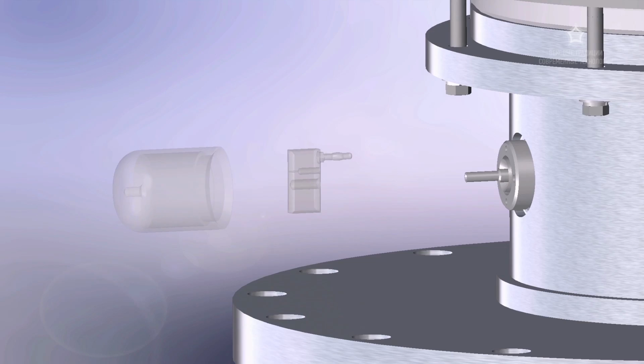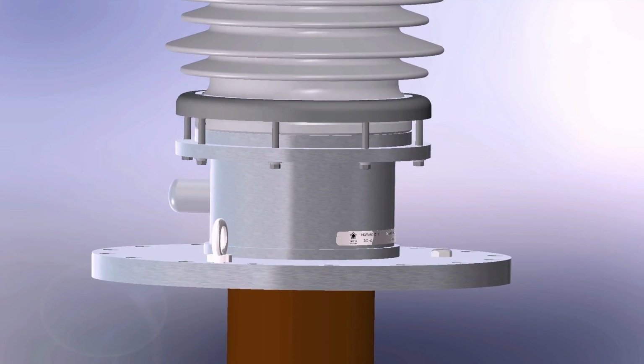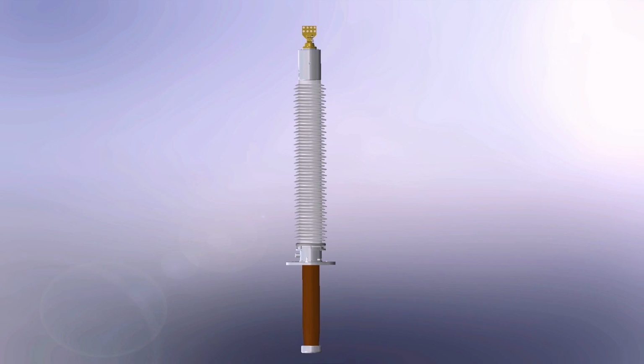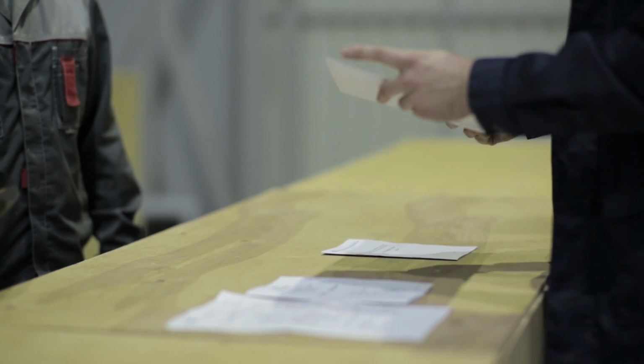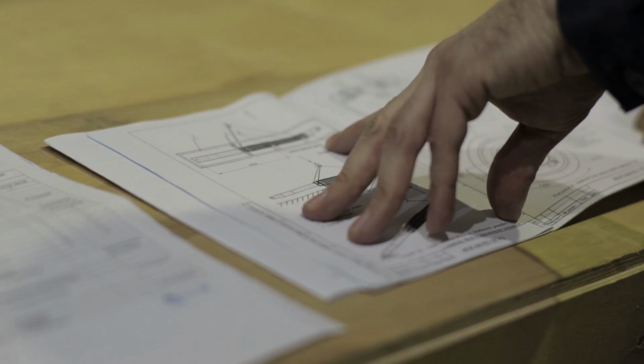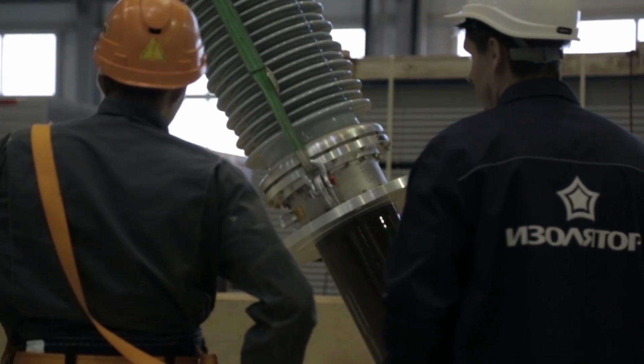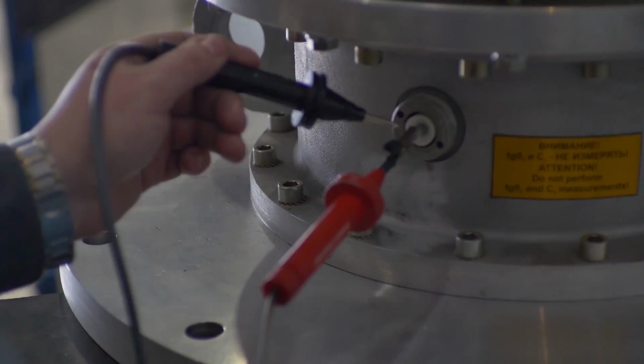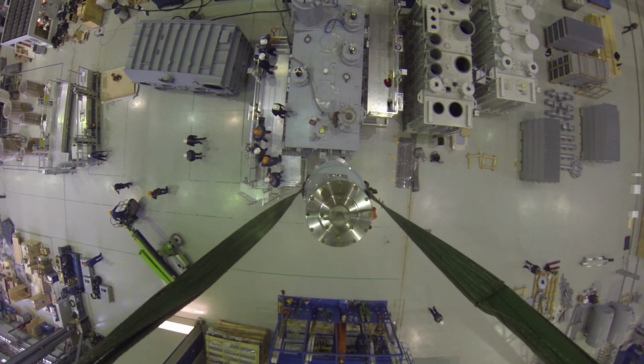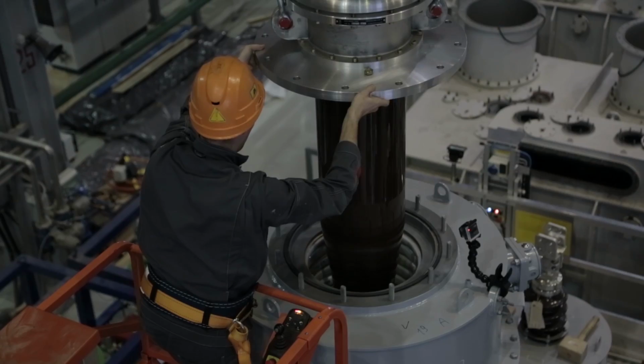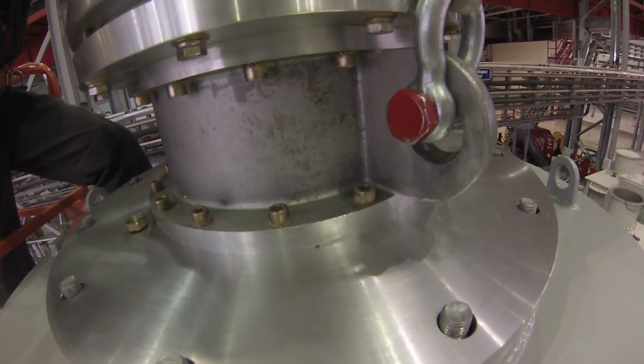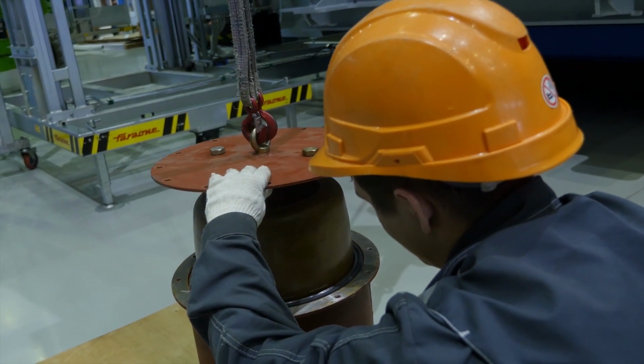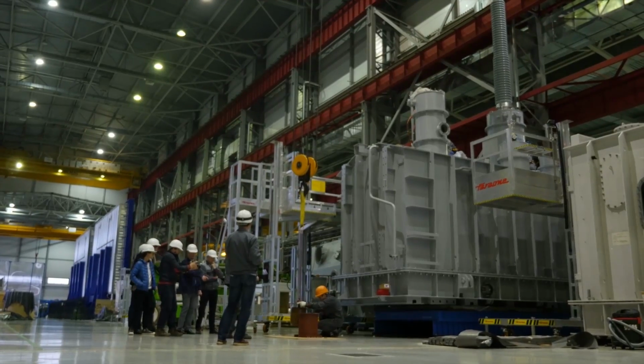This is a video instruction on Izolyator RIP bushings installation. The film details a 500 kV bushing bottom terminal connection and a 220 kV draw-lead transformer bushing installation process. Bushings with oil-filled porcelain external insulation are used as demonstration samples. Bushings with other types of external insulation are installed similarly.